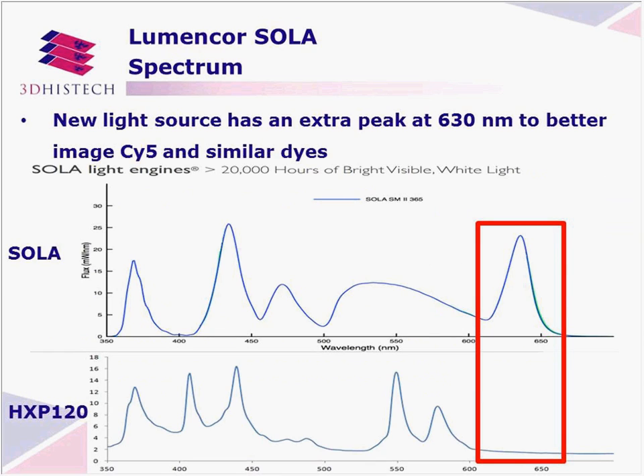Here are the spectra of the HXP 120 and the SOLA light source. What you can see here, the first peak is the epi illumination. Actually, the SOLA has two versions. The peak is around 400 nanometers, or 365 nanometers. We select this version because it currently fits the filter blocks better, and is also better for excitation. And here one peak is missing compared to the HXP 120 around 400 nanometers.